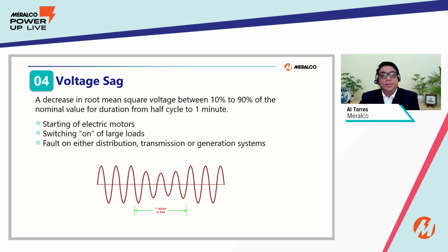And lastly, voltage sag problems. So voltage sag is considered the most common power quality problem. In layman's terms, voltage sag is commonly referred to as voltage fluctuation. So kadalasan yun ang tawag, voltage fluctuation. As defined by the Philippine Distribution Code, it is a decrease in root mean square value of between 10% to 90% of the nominal value of voltage for a duration of half cycle to 1 minute. So kadalasan napakabilis lang ng voltage sag, usually split second nga, no? And typical causes are starting of large loads, starting of motors, and faults on either the distribution or transmission system.